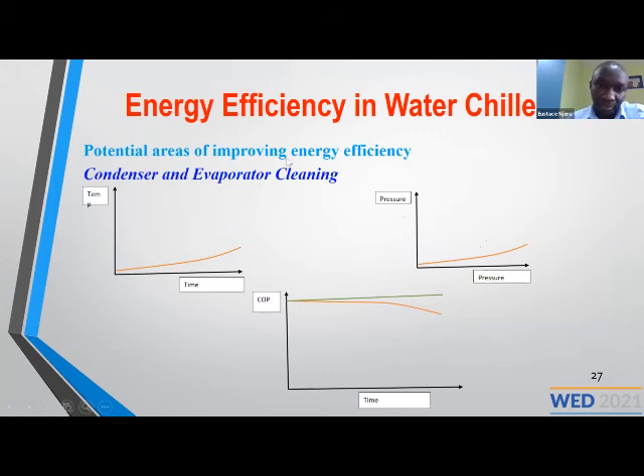This one has to do with the cleaning. You need to have a system for monitoring the temperature drops, the coefficient of performance drop, and the pressure drops within the system, especially for air-cooled systems, so that if you reach, for example, a certain point, you know that's the best time to switch off. Because if you continue running at this point, you'll be wasting a lot of energy. There will be a lot of poor heat transfer between the refrigerant and the water being cooled. So that one is very important.